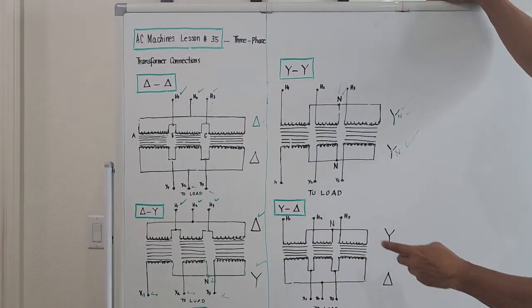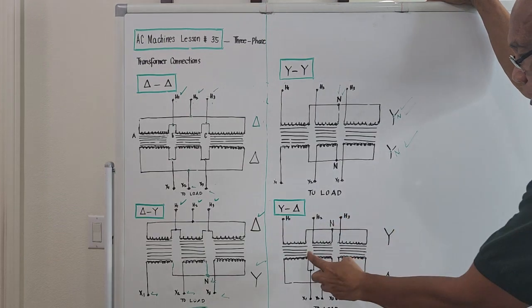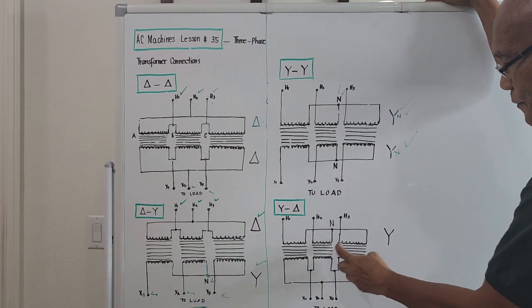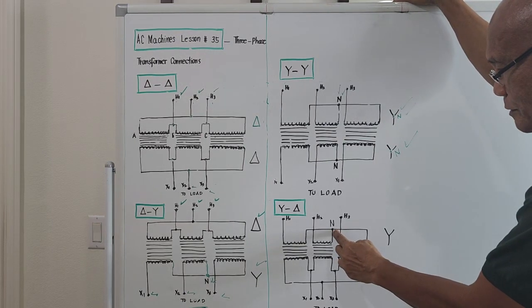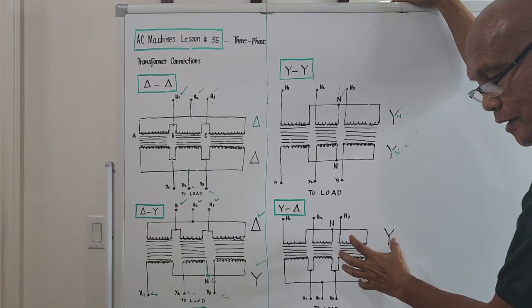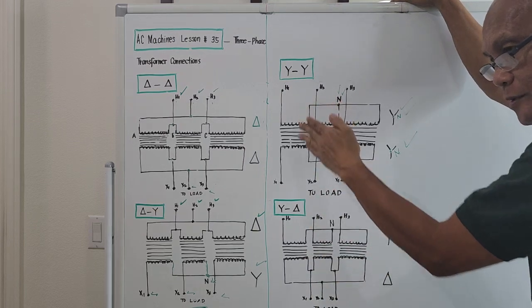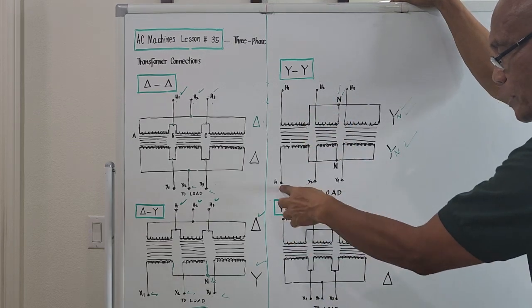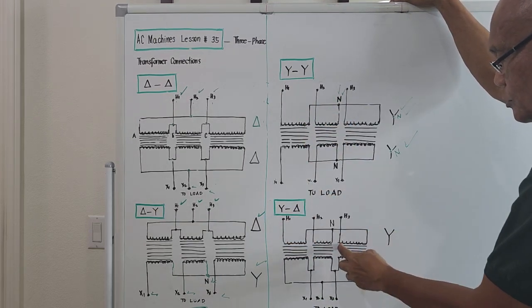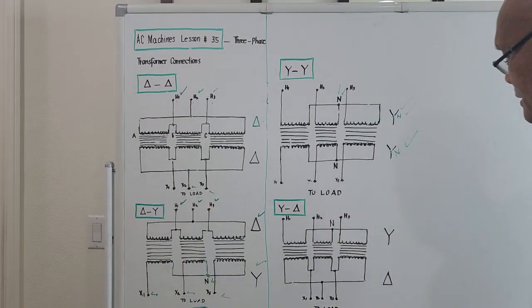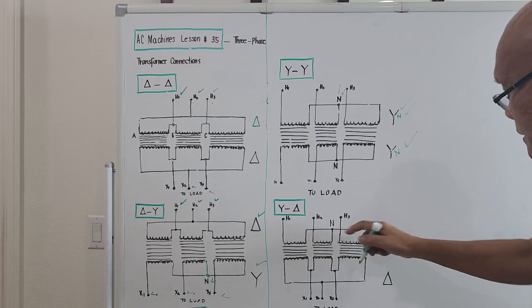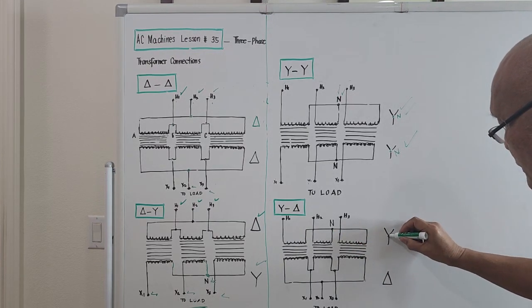So we will be having a neutral point. This is left, left, left. We merge it into one. We connect it to neutral point N. Okay, so the remaining other ends we will bring out. So this will be H1, this will be H2, this will be H3. So these are the primary lines. Okay, and this neutral point in here is this one. It should be here.